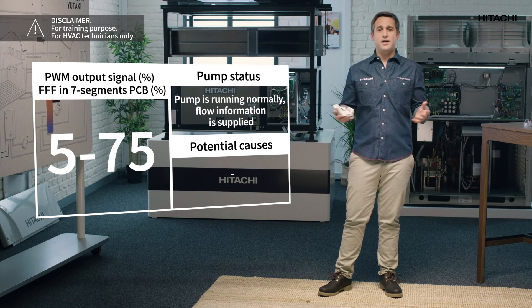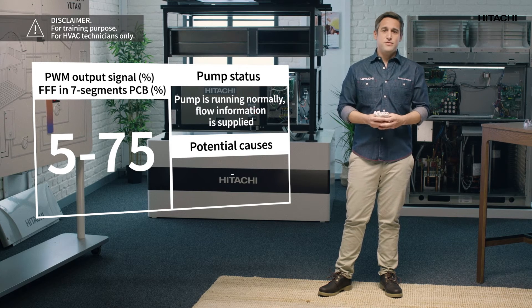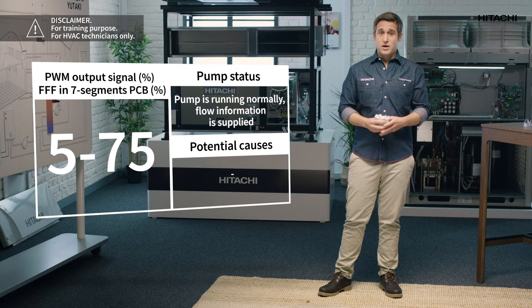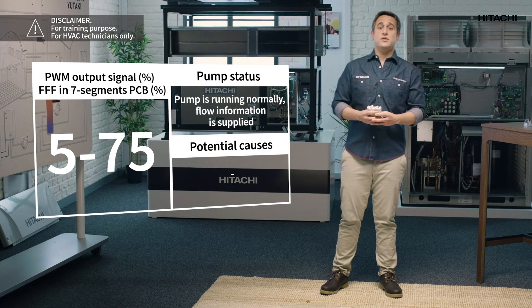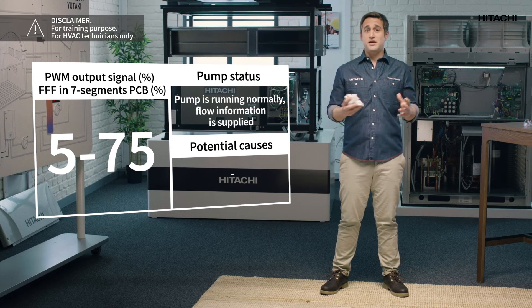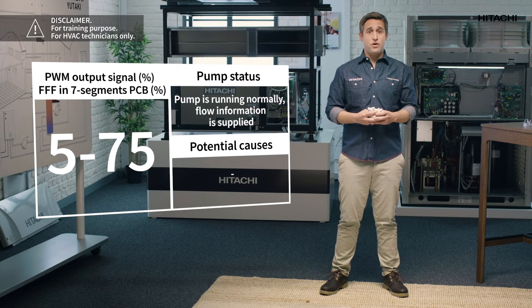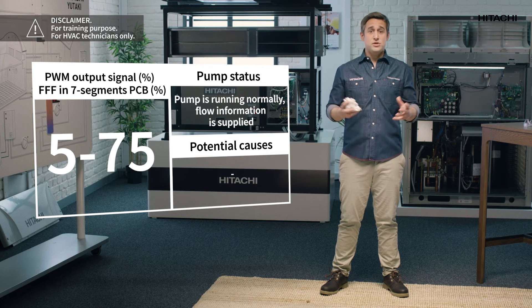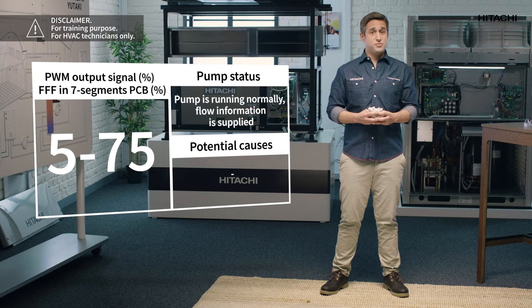Values of 80, 85, and above are fixed values — each value means a different problem of the pump itself. Notice that when the pump is sending a problem signal, the PCB cannot read any flow rate, so the LCD display shows zero cubic meters per hour.